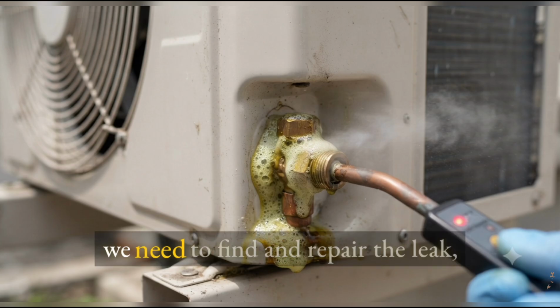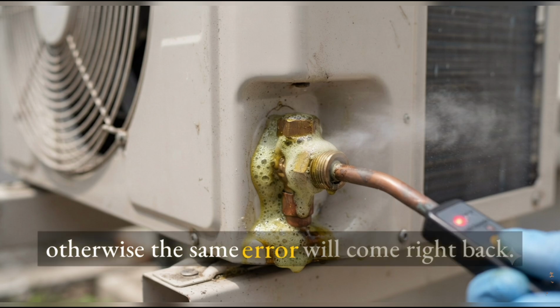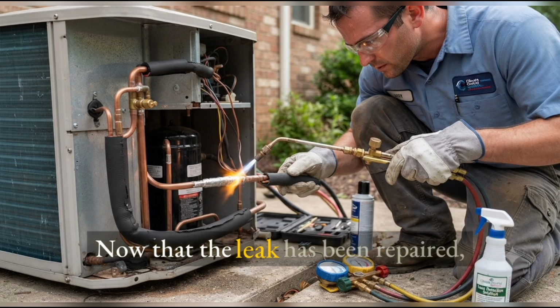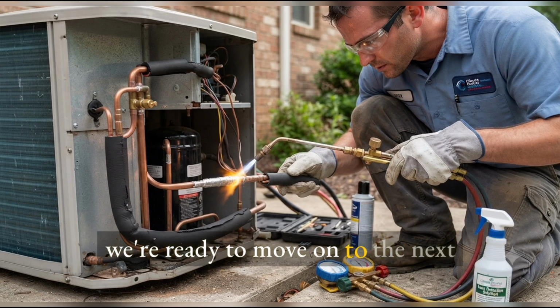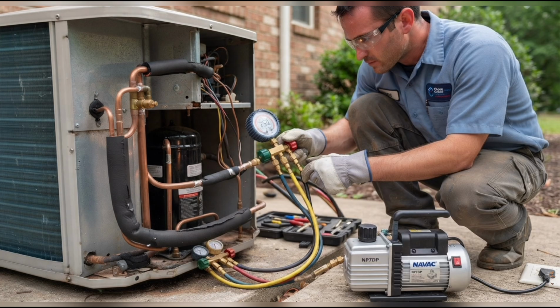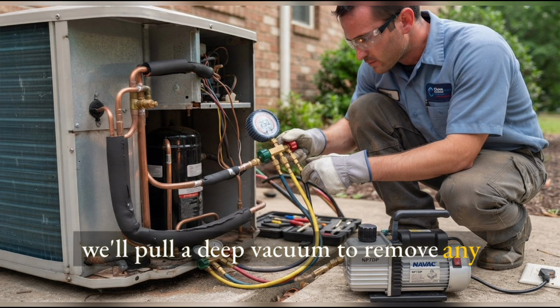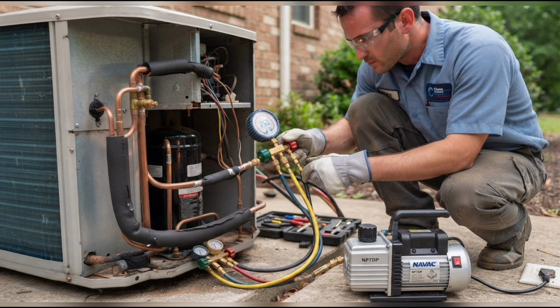Before adding refrigerant, we need to find and repair the leak, otherwise the same error will come right back. Now that the leak has been repaired, we're ready to move on to the next step. Next, we'll pull a deep vacuum to remove any air and moisture from the system.